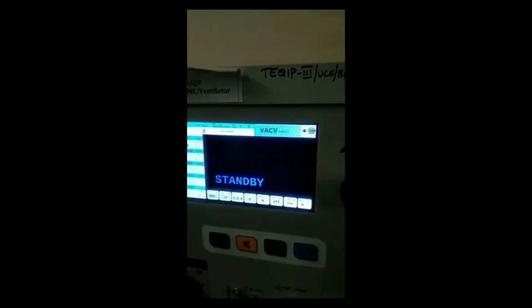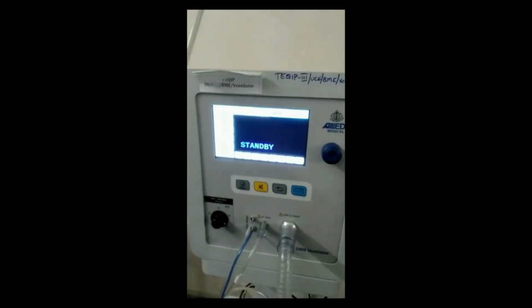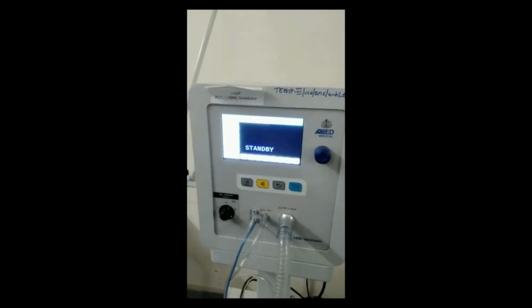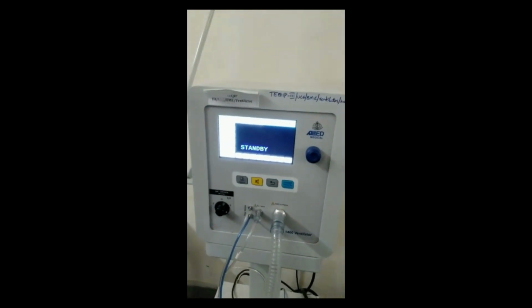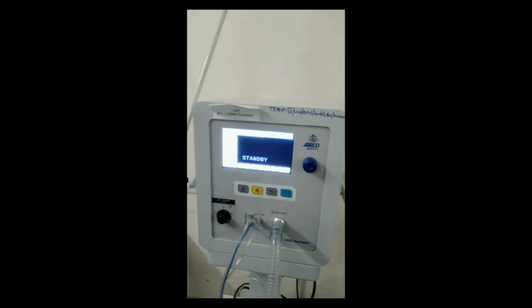We can see that here the calibration has failed because we have not connected the oxygen cylinder to the ventilator. If we connect the oxygen cylinder to the ventilator and calibrate again, we will pass the calibration test. So this is all about the calibration test of the ventilator.